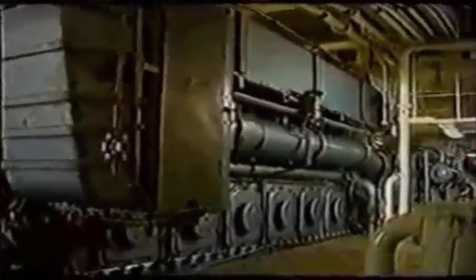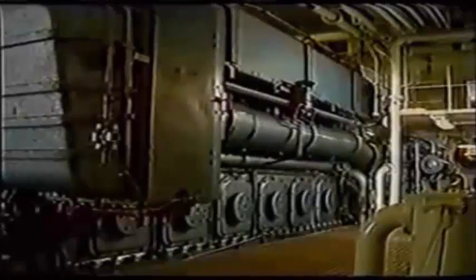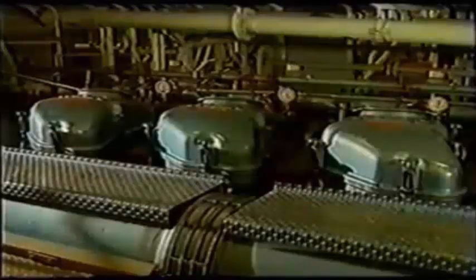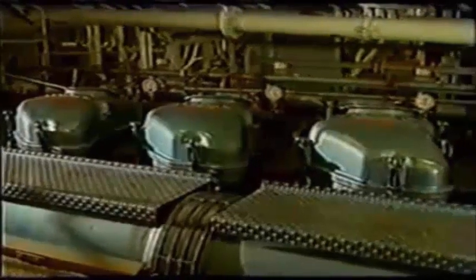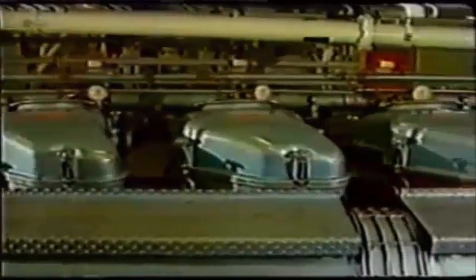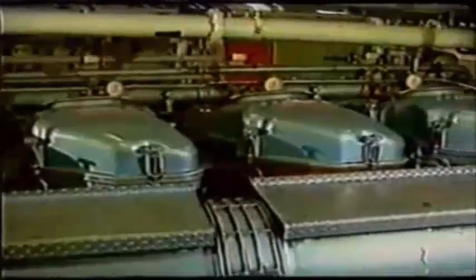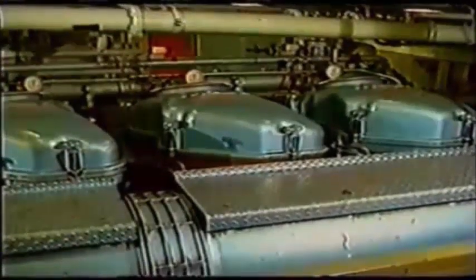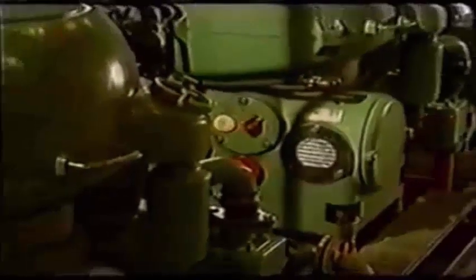Due to vital design differences, in the case of medium-speed diesel engines, the cylinders are open to the crankcase. This means that the crankcase oil can be contaminated by corrosive combustion products. The chosen system oil must deal with these contaminants as it lubricates the system. The lubricant must also maintain effective lubrication under high mechanical and thermal loads, and must transport solids from the cylinder to the cleaning devices, such as filters and centrifuges.